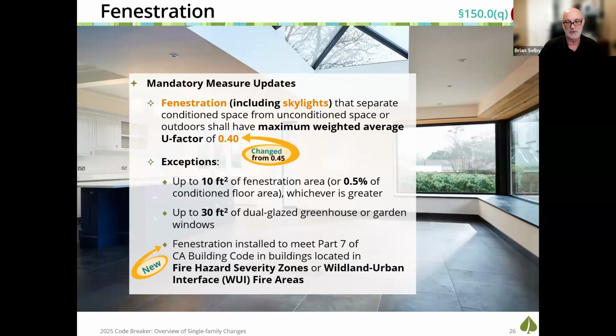So in the 2025 code, we're going to see those maximum U factor for fenestration, that includes vertical glazing as well as skylights, cannot exceed a maximum weighted average U factor of 0.40. So this could be tough for remodels. In some cases, clients want to reuse existing windows. If that window is not NFRC rated, it's never going to meet that 0.4 U factor. So make sure that information is available on the plans and those projects are meeting the requirement.